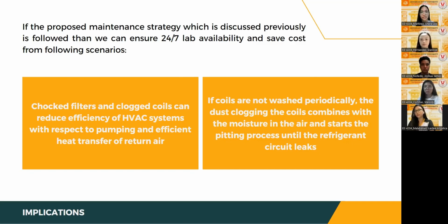This case study was carried out by Goodway Technologies Corporation, which provides cleaning solutions for HVAC systems. If coils are not washed periodically, the dust clogging the coils combines with the moisture in the air and starts the pitting process until the refrigerant circuit leaks. And if the refrigerant circuit leaks, then repairing it will incur a total cost of 67,100 as indicated in table number 3.